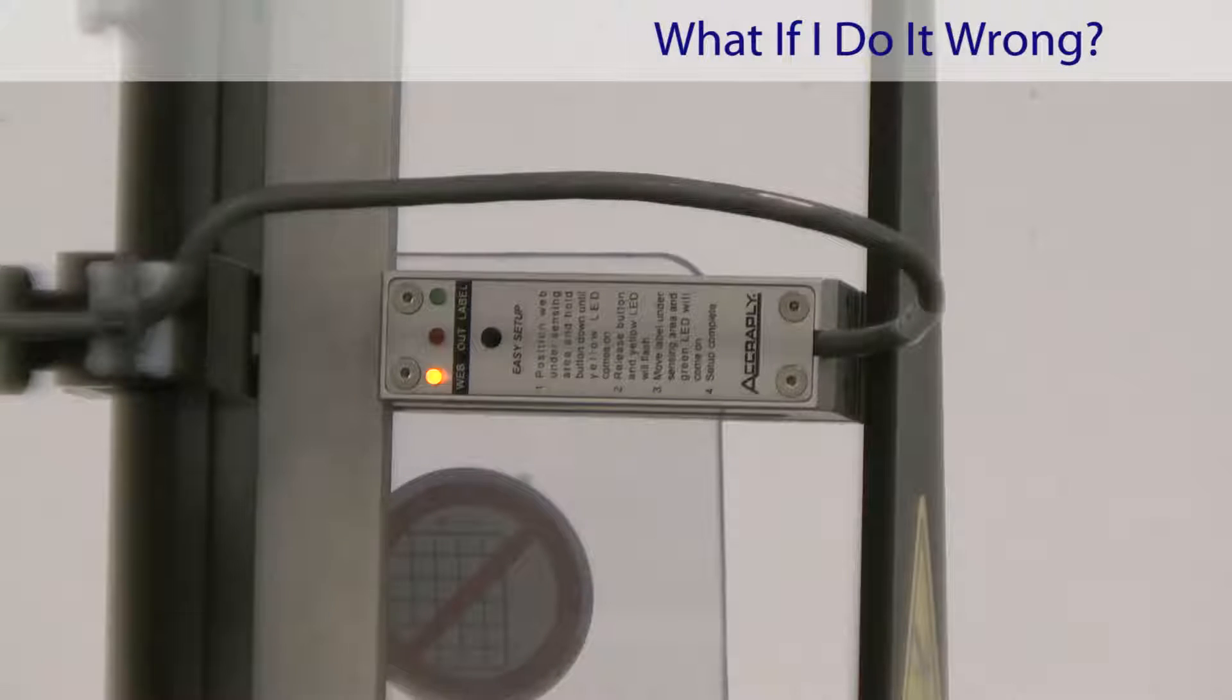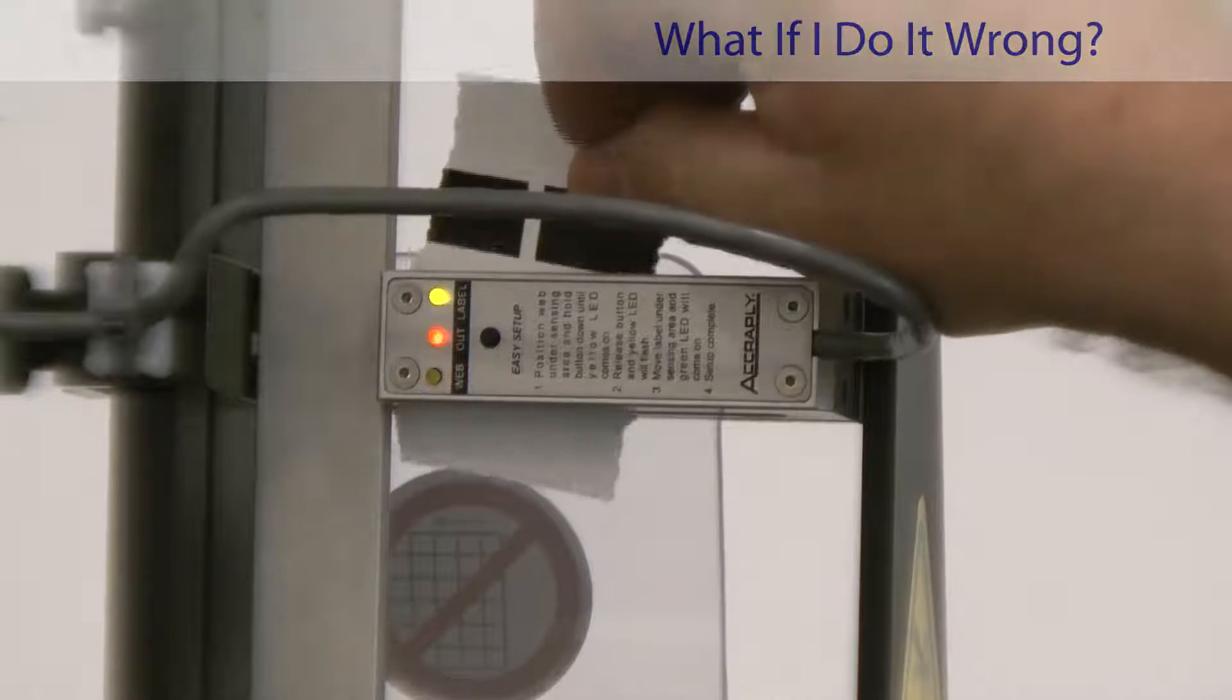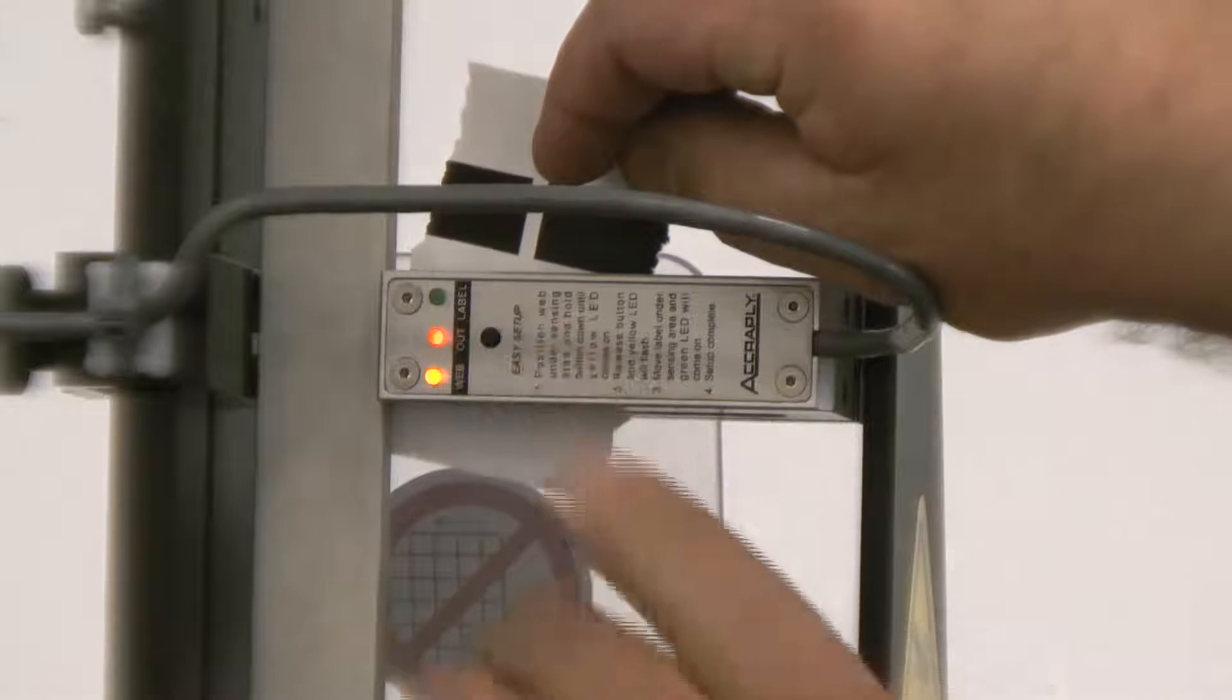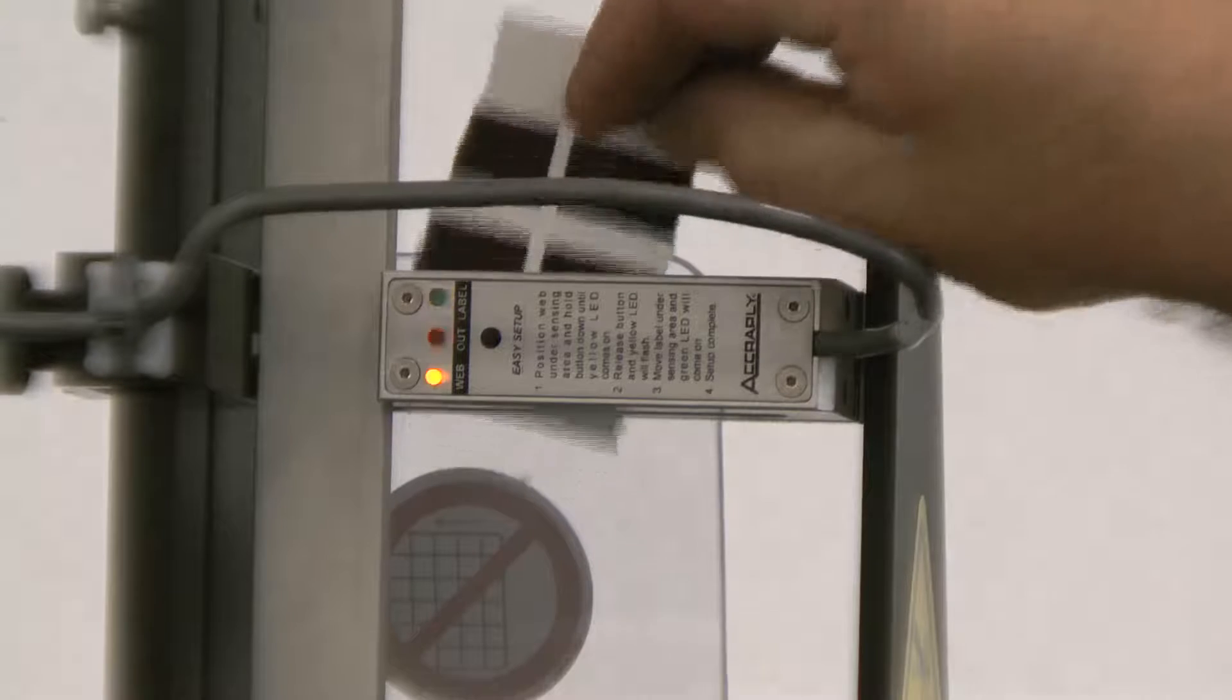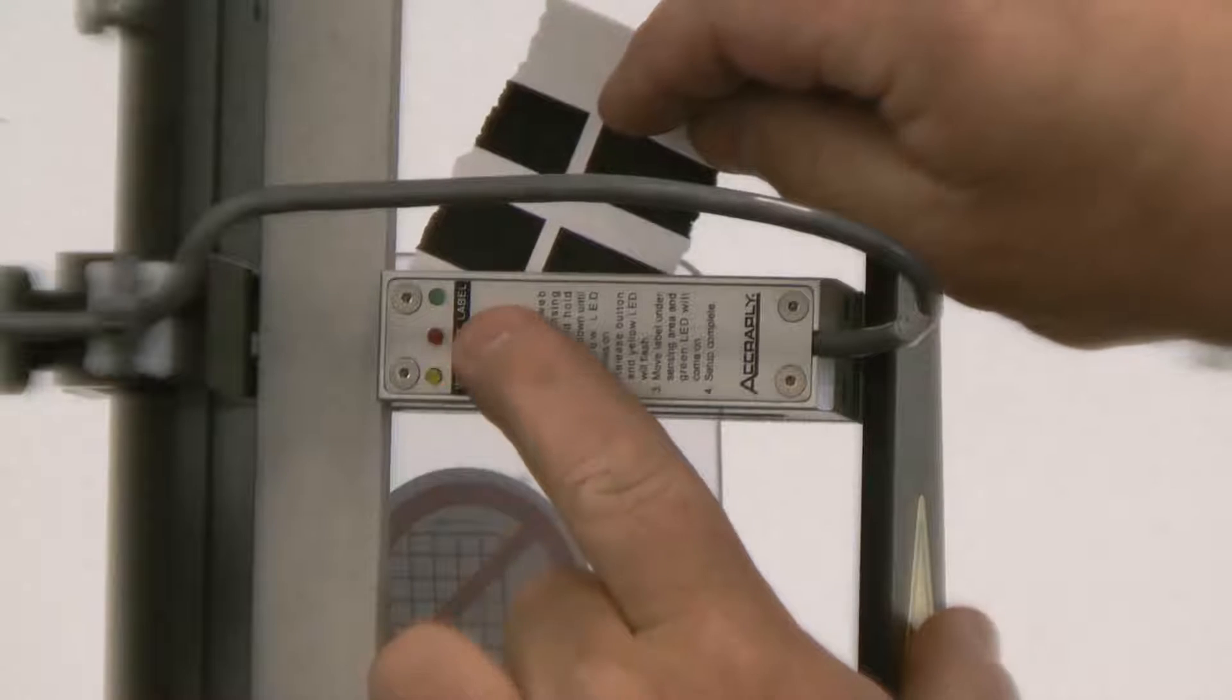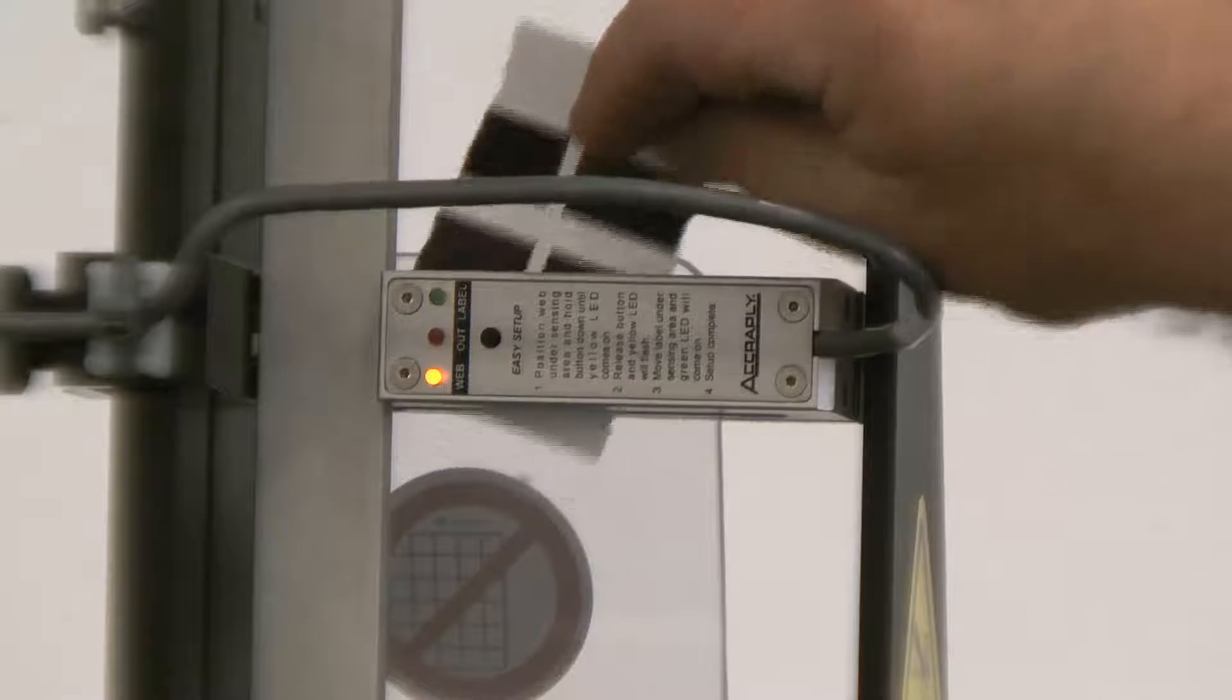When training the label sensor, if you happen to put the black portion under the photo eye when you push the train button, the sensor will alert the operator by blinking the red light. In this case, you must remove the material, put the white under it, hold the button down again, and train the sensor.